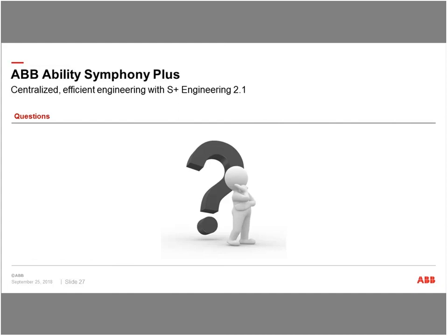To add to that, the manual exporting of the database from Composer and importing in S+ Operation is what is eliminated. With an integrated database between engineering and operation, any change that's done in engineering is automatically pushed into operations. So now you don't have to worry about manually updating the two databases and keeping them in check. That is just automated into the system now.